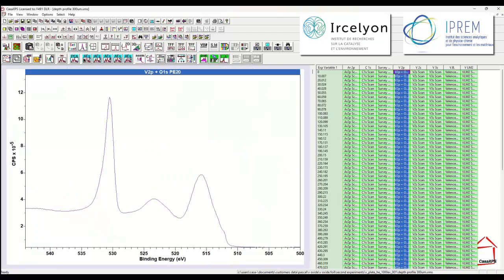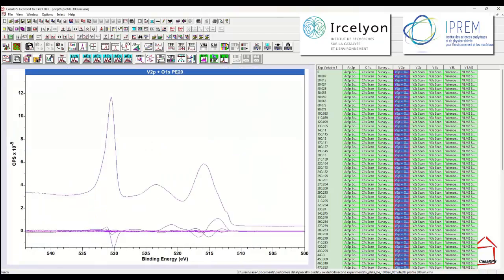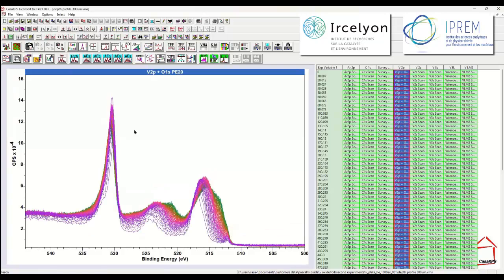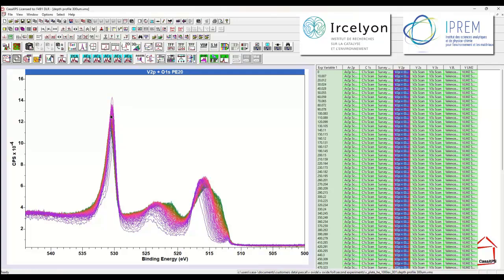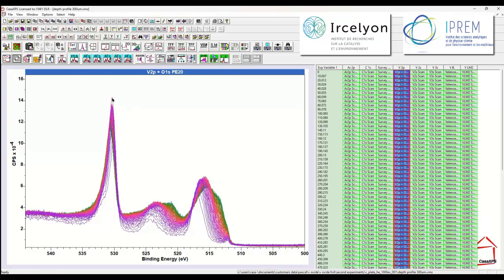Oddly, I'm going to do this by a relatively low-tech solution, and that is I'm going to display the data overlaid and reset so we see the spectra, and then make an observation. And while we see lots of changes occurring in these data, there is one change that looks to me slightly anomalous, and that is, out of the blue, there's one spectrum that leaps up above the other spectra that are related to the oxygen 1S. There may be something in here that I can't see too easily, but for some reason the oxygen 1S is throwing out one spectrum that is perhaps an outlier. So I'm going to hold the CTRL key down and the SHIFT key down at the same time, point at the spectrum and click.